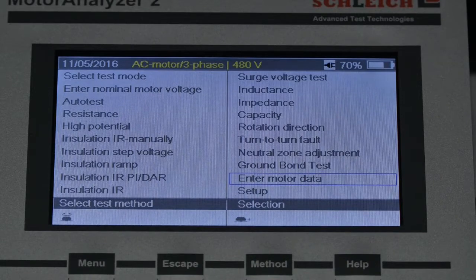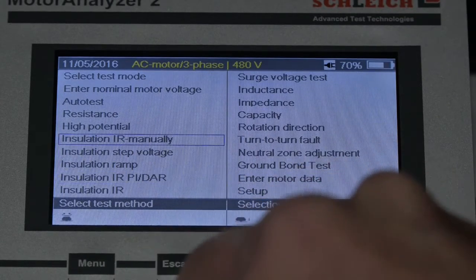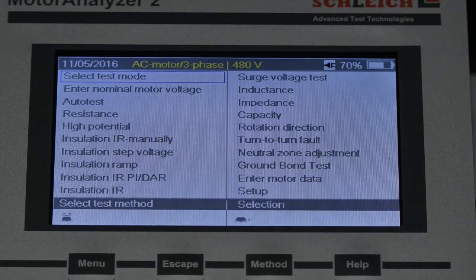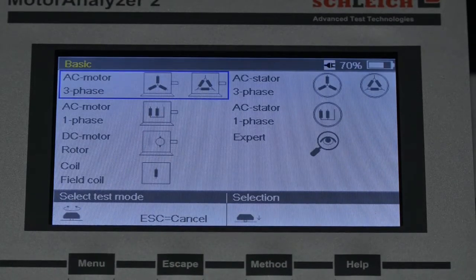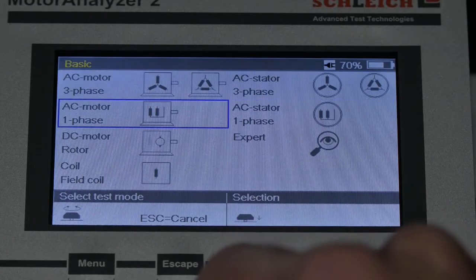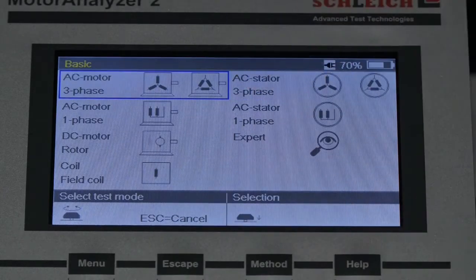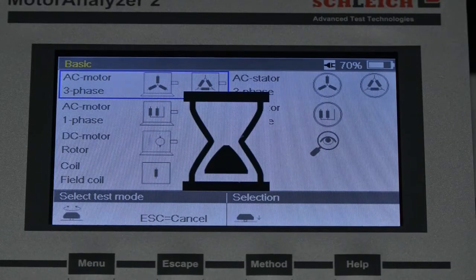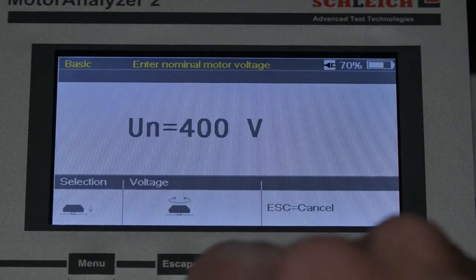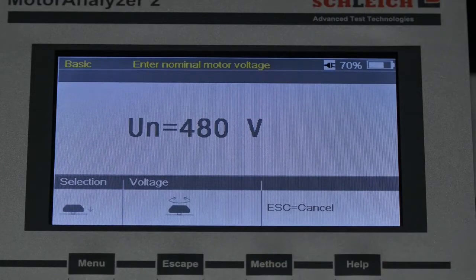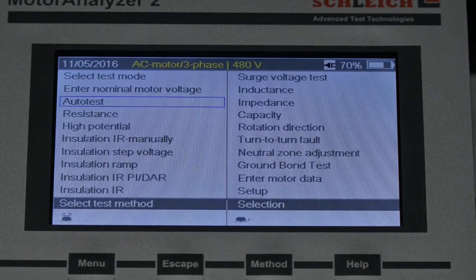Now that we have our motor data entered, let's select the test mode that we want to use. Since we have a 3-phase AC motor, let's choose the 3-phase AC motor option. This particular small motor is actually a 480 volt motor. By setting this value here to 480, the unit will automatically calculate the proper test voltages for this motor. Now the only thing left to do is do the test.